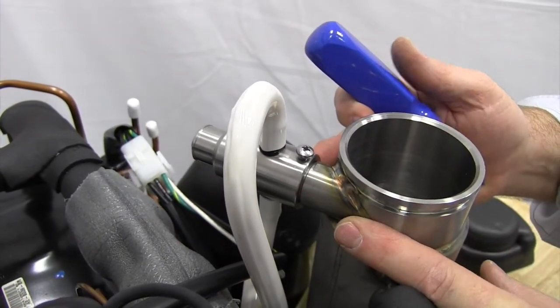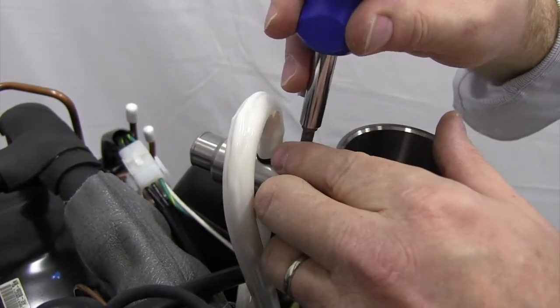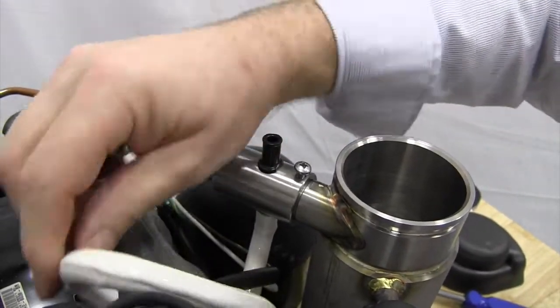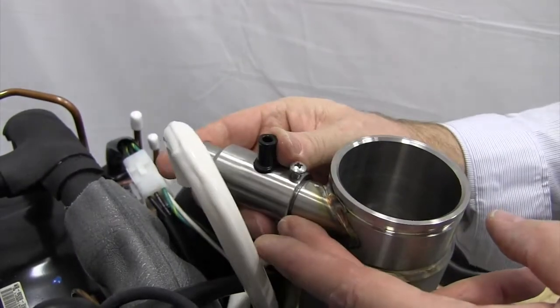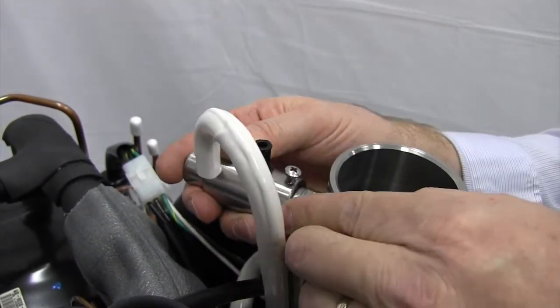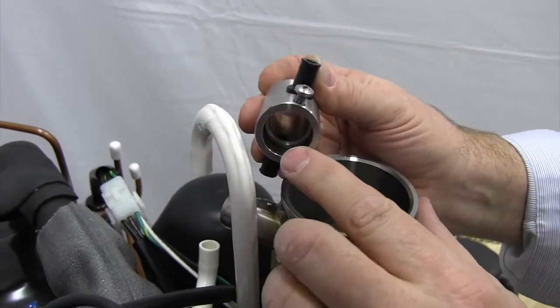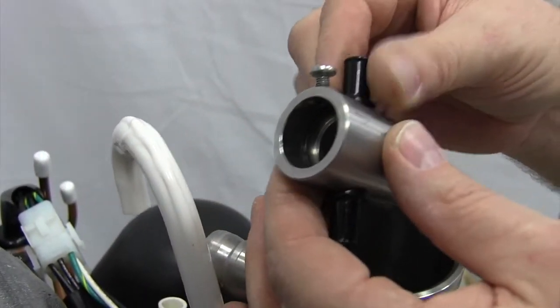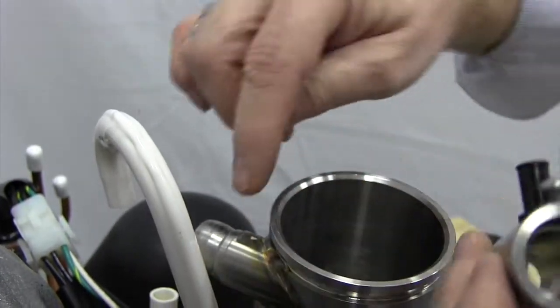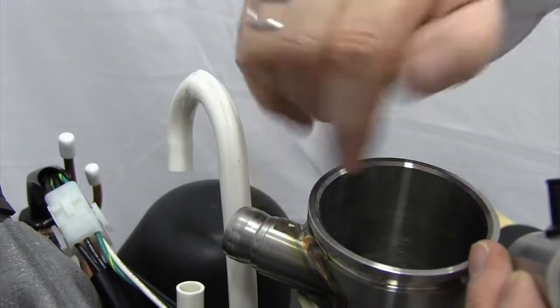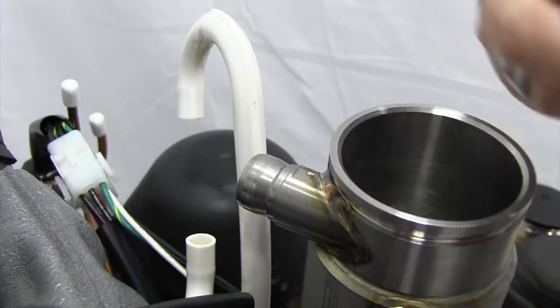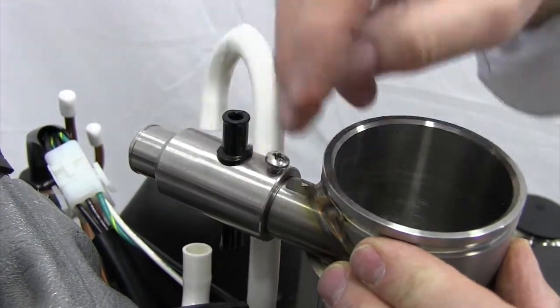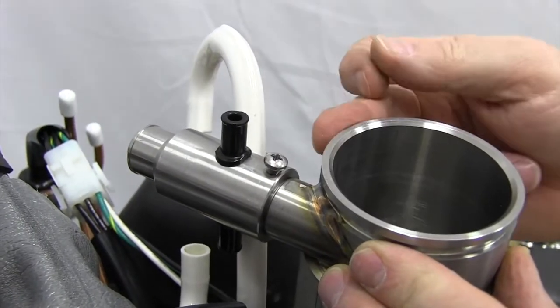On the 425, the compression nozzle now has an O-ring in it. So we loosen up our set screw on the top here, remove my two drain lines from the nozzle, and then I can slide the nozzle off. The nozzle now has an O-ring on the inside - it's sealed up really nicely. Also another change from our older design: our set screw now goes onto a flange, onto this shoulder here of the outlet. As you tighten this down, it tightens onto that shoulder. The screw no longer goes down into the path of the ice.